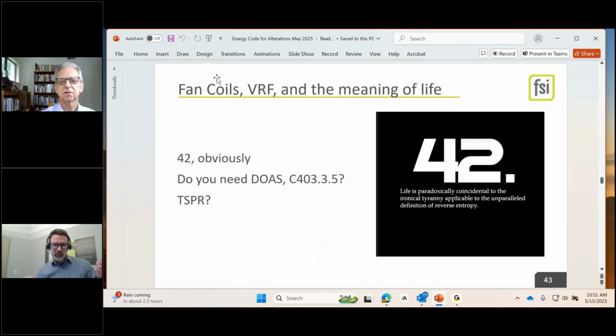Do you have TSPR? Do you need DOAS? Can you not do DOAS? What are you doing for equipment? The answer was often split systems indoor, or even a rooftop unit indoor without any outside air, and then a separate energy recovery unit. And for flexibility, just for the ability to go very high or very low, or lift from ground level to 10 stories, the answer was often VRF. It just is. And let's do the next slide.